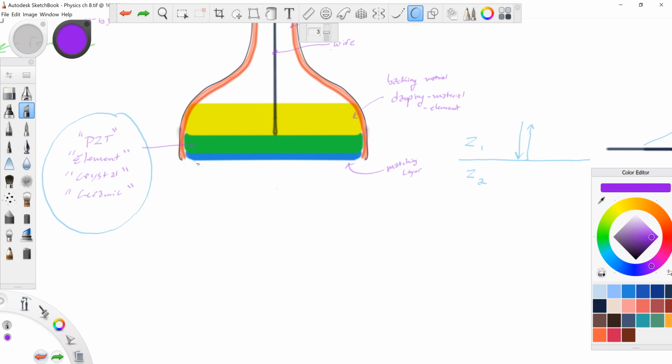Okay. That's what the matching layer is for. The impedance of the piezoelectric material is about 20 times greater than soft tissue. The matching layer, and here's a little trick that the book doesn't mention, there's oftentimes multiple matching layers, and each matching layer is kind of like, let's see, if we have a house here, and then we have a floor down below, and so here you are.